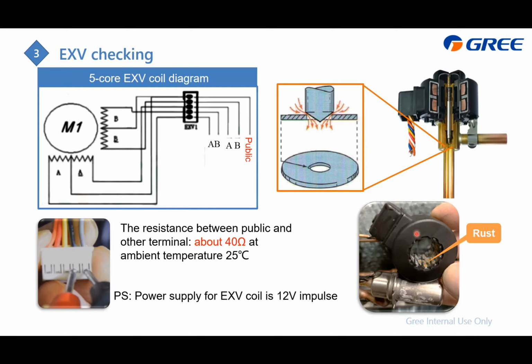And here is the EXV coils, and you can also find that. In this case, if there's some rust here, it will also lead to the control not being that good. For this one, you just replace this one. This coil is okay. And if you just worry about the coil, you can also check the resistance value. It should be about 40 ohm when the ambient temperature is 25. You can just check the pair with this A or B, or minus A or minus B.